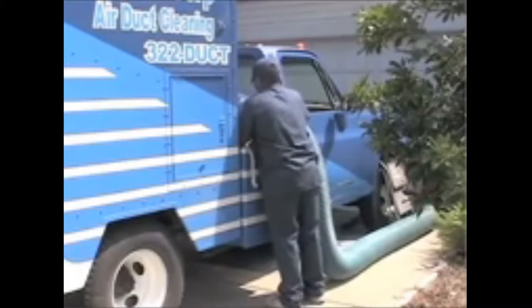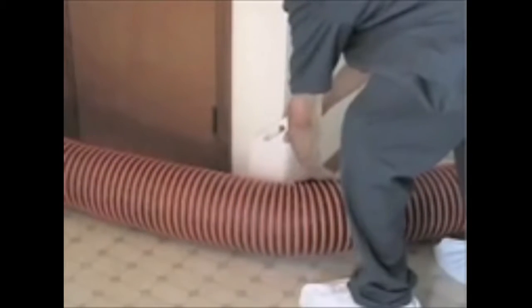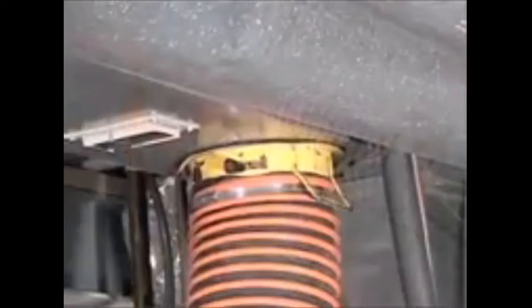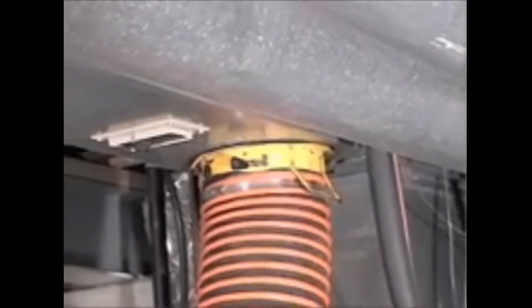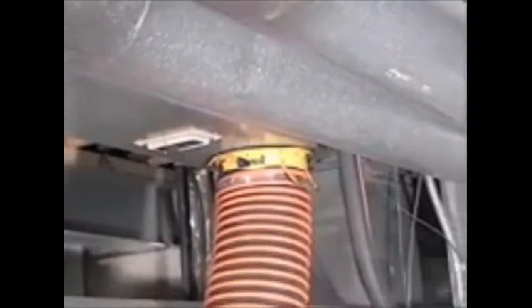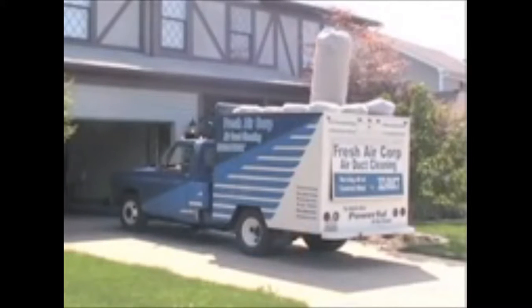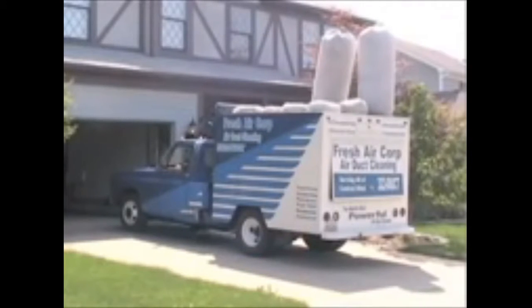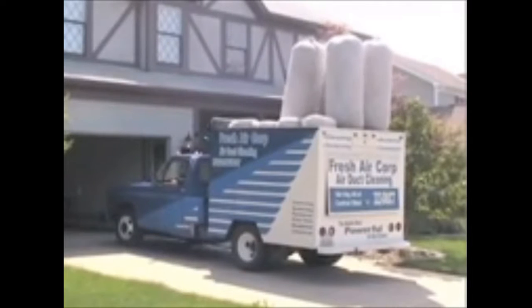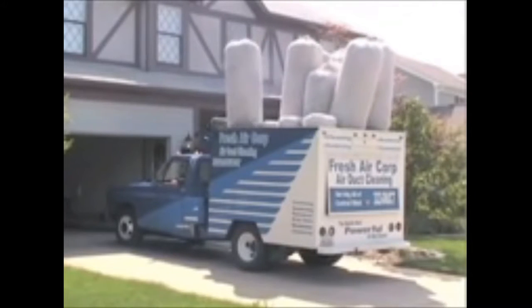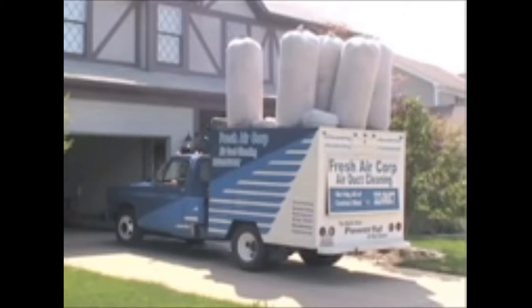Our orange hoses are only used indoors, and protective edge guards are placed at all corners and doorways. The hoses are connected by soft, flexible canvas wraps, and a special connecting boot allows us to attach the hose directly to the main trunk lines and cold air plenums. Now, the Monster Vac can be started up. Although the vacuum doesn't actually do the deep cleaning, the huge reverse airflow makes a perfect air highway for the removal of the dirt, dust, and contamination.